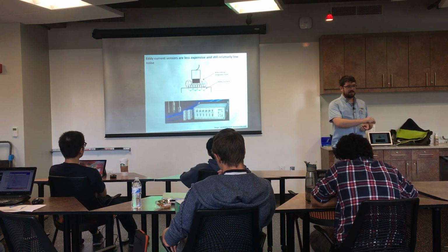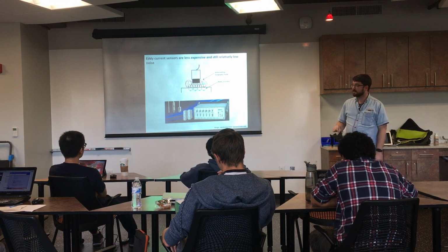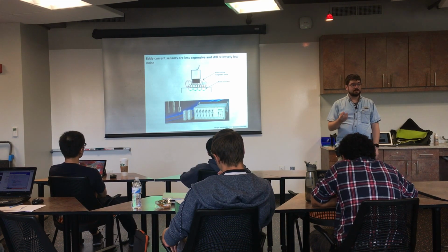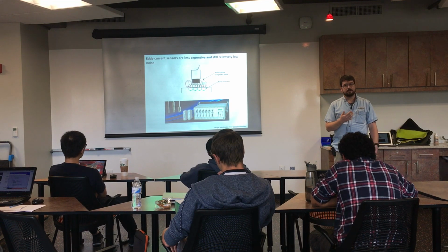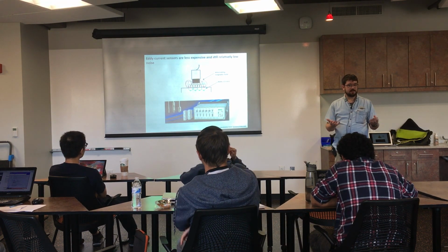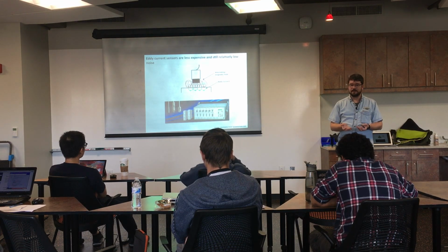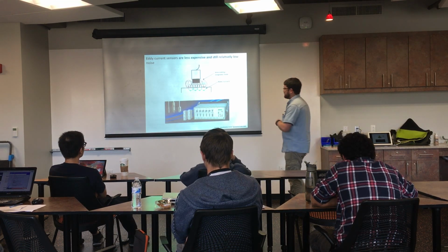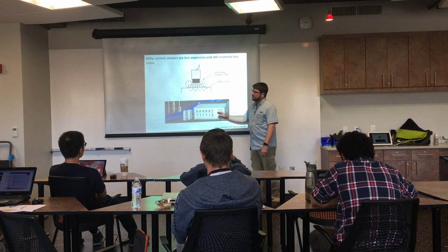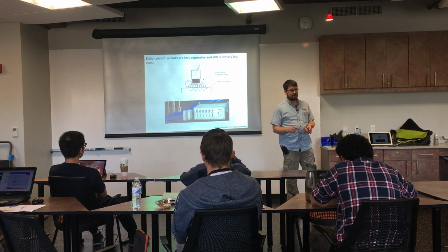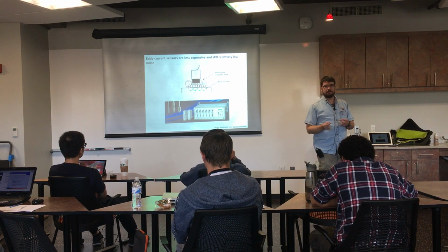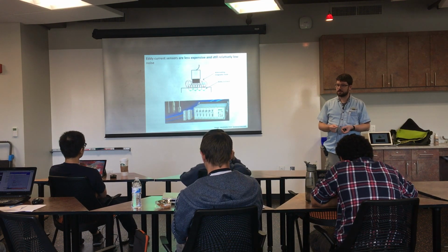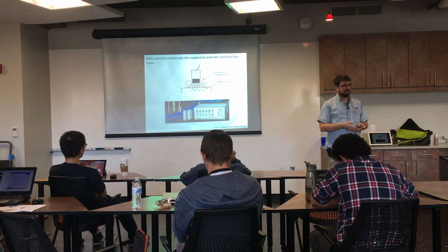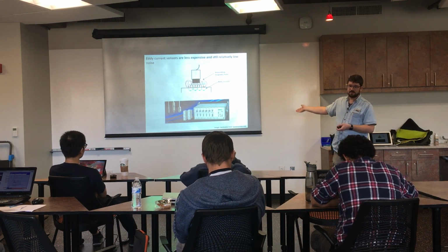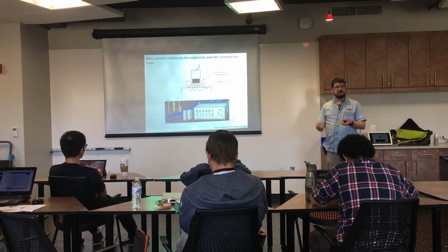The capacitive sensor is the highest resolution of any of them that we're going to talk about. They're also relatively expensive. One sensor that has a range of about 6 to 8 millimeters, the sensor plus the signal processing electronics, are about $5,000. So they're not cheap. They're much more expensive than LVDTs. Eddy current sensors are cheaper than capacitive sensors. They have about an order of magnitude less resolution. A capacitive sensor can have tens of nanometers resolution, an eddy current sensor hundreds of nanometers, and an LVDT a micron or so.